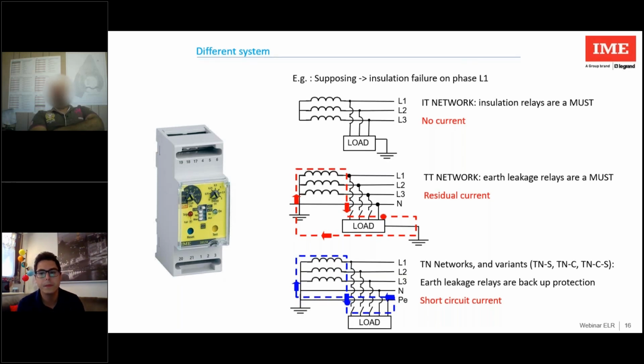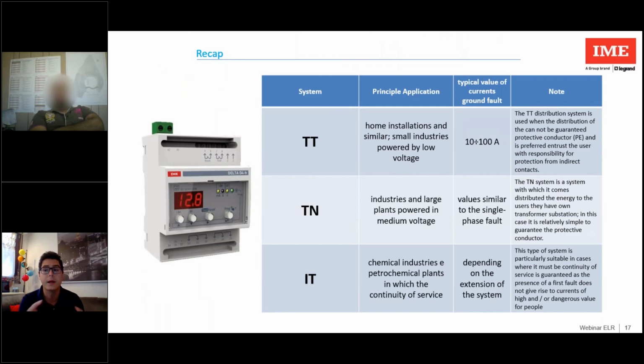Well, in this slide, in this table, we summarize the various systems indicated and the main applications. For example, the TT system we find in home systems or in small industry that use only low voltage. The TN system, instead, is powered in large industry or in medium voltage. And the last, the IT system, is widely used in plants where I have to guarantee the continuity of the service, such as chemical plants or petrochemical industry.